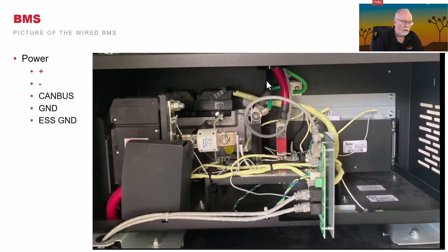When it's finished connected, this is what it looks like. So effectively you'll see my negative is coming down from the inverter. It's tied directly to the negative terminal, and then the ground is on top of it. That's your stack. And then you'll put your securing washer and tighten it to the torque specifications. The positive, same thing. Bring the positive down, connect it. Make sure that your neutral ground is in place. Make sure that your inverter ground is taken up.